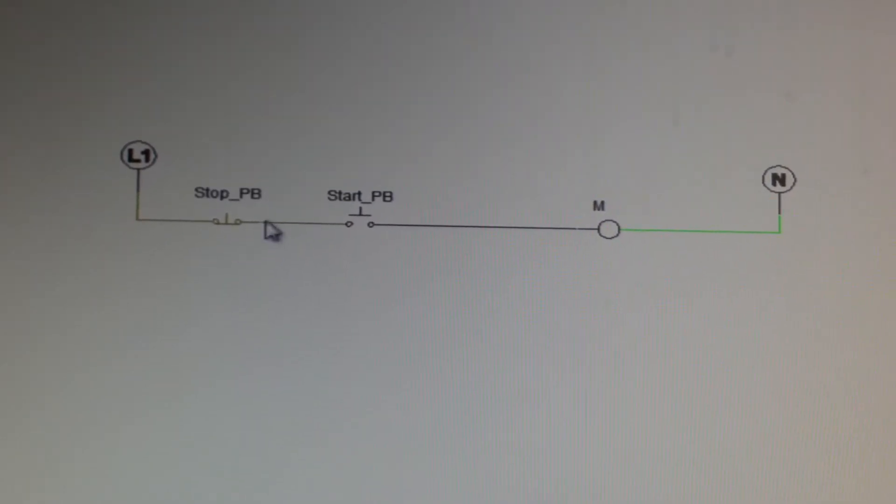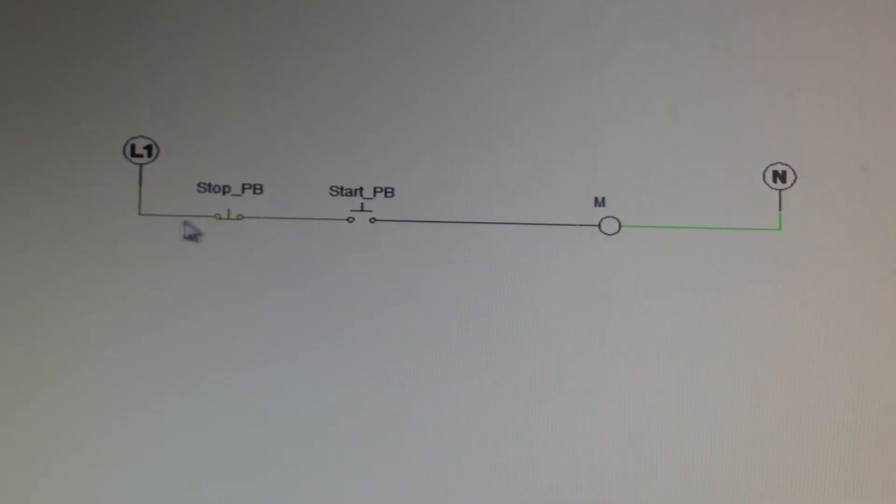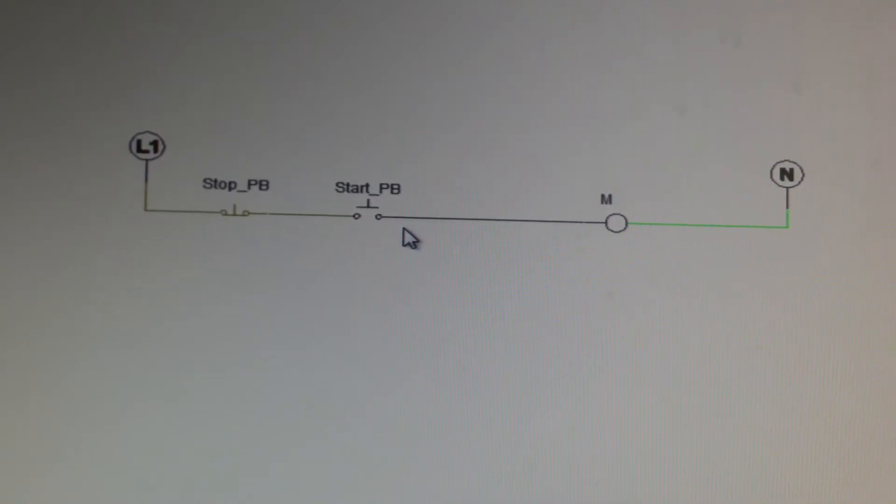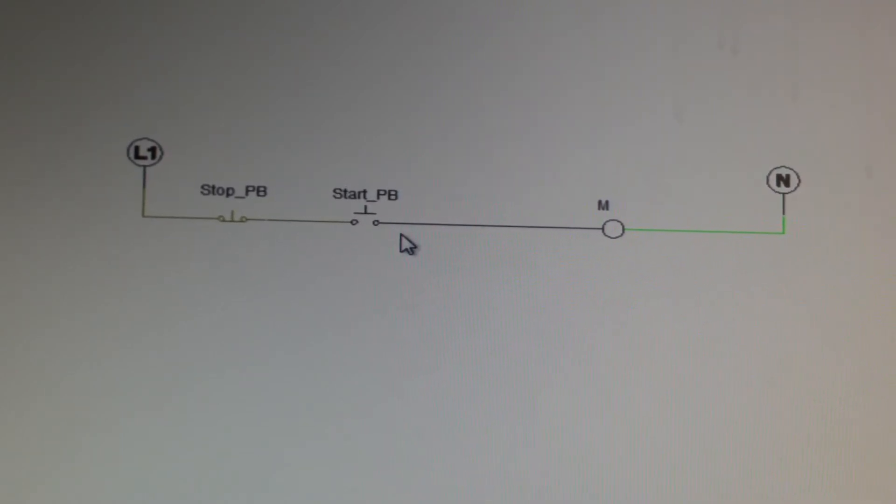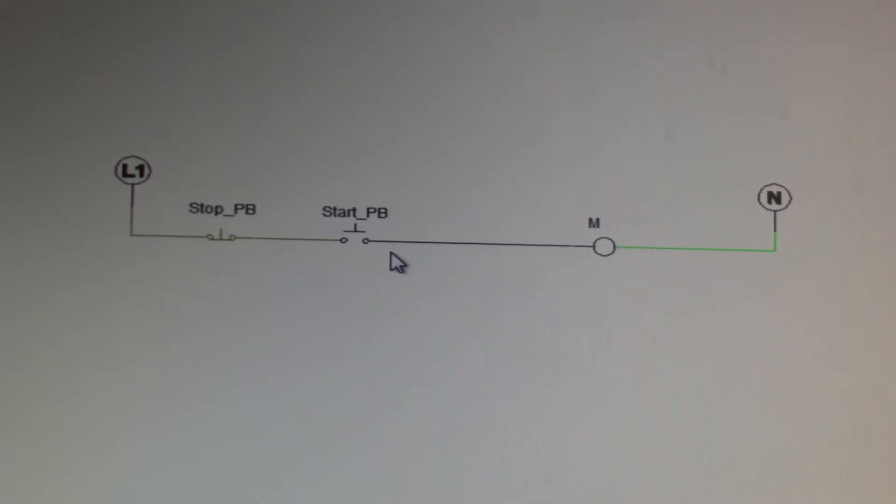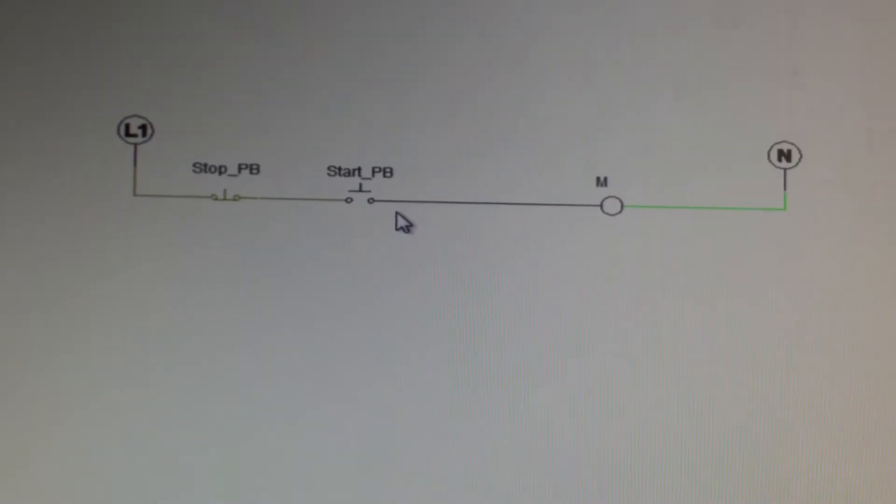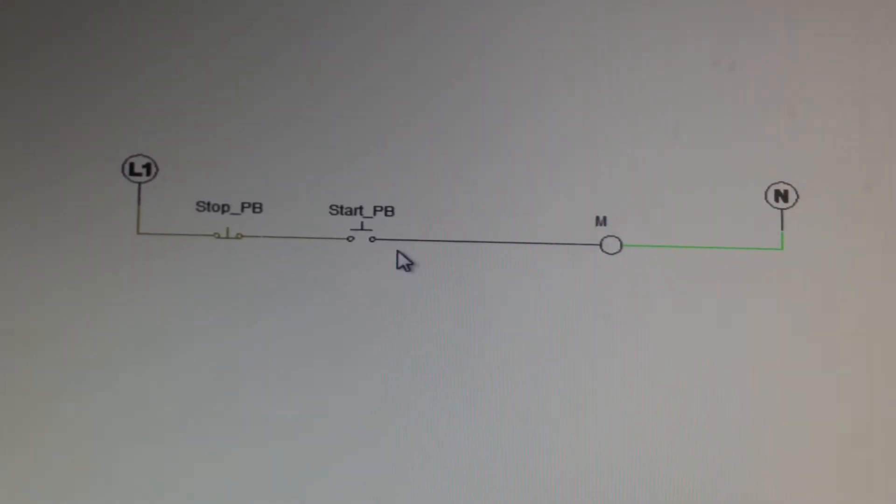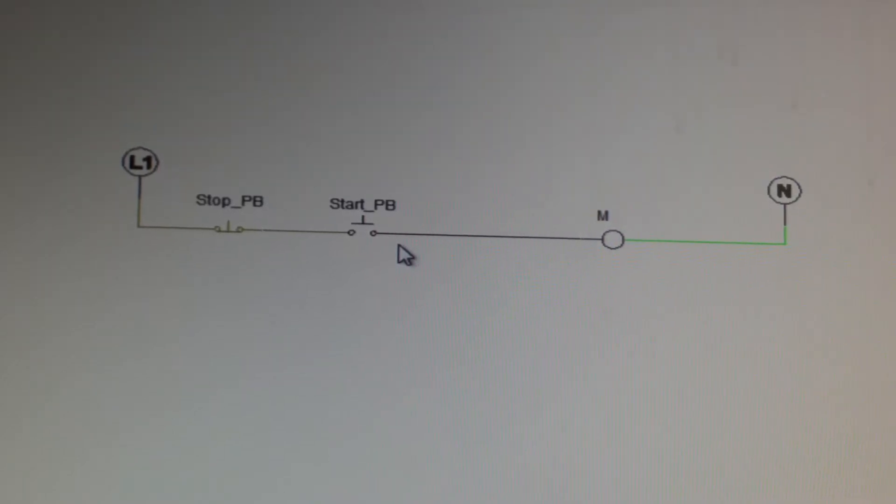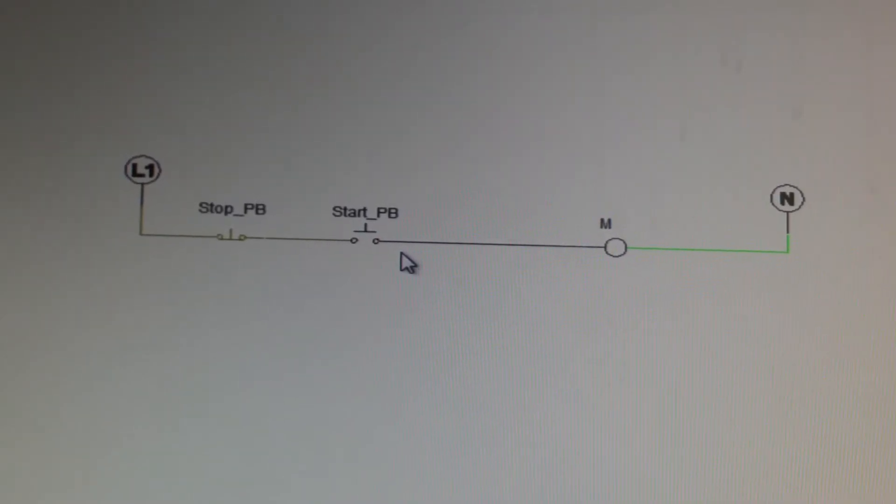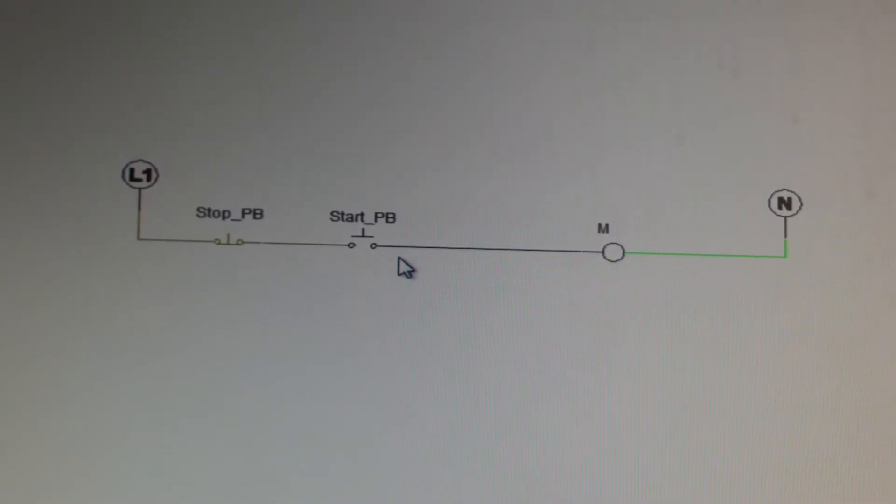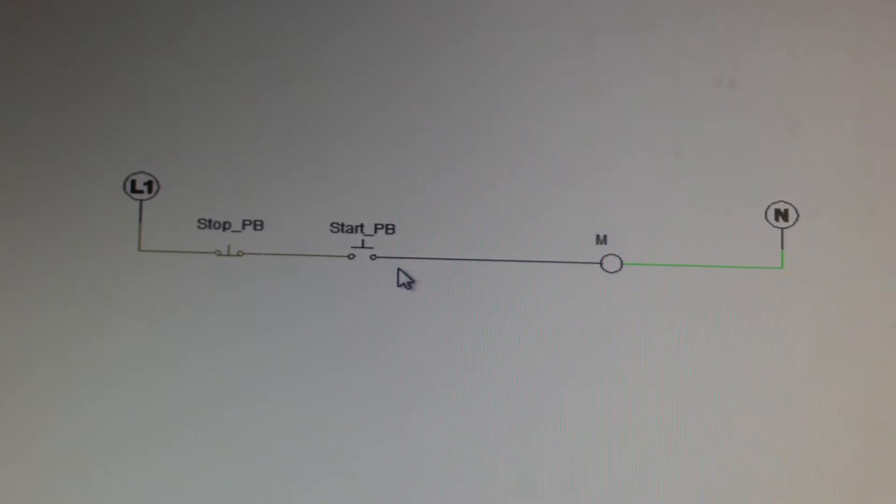So this stop button that we have on our circuit, the way it's drawn here, whenever we look at a component on a wiring diagram, it's always drawn in its non-actuated state. When I say non-actuated, I mean that there's no outside influences causing it to move. These here are push buttons.